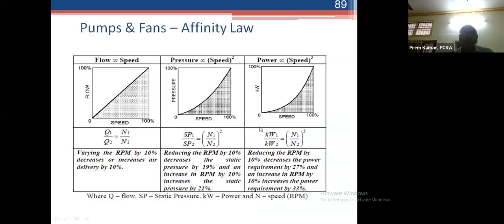The pumps and fans follow the affinity law, both follow the same rule. You see the pumps, let us discuss the case of pumps and extend it to the fans also. During summer, pumps are to work more. During monsoon season, it is to work less. The choice is to have two different pumps. One smaller pump for the monsoon season, larger pump for the summer season. The other option will be going for VFD.